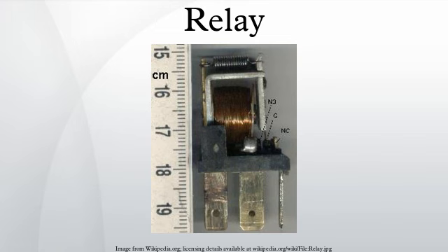Derating factors: control relays should not be operated above rated temperature because of resulting increased degradation and fatigue. Common practice is to derate 20 degrees Celsius from the maximum rated temperature limit. Relays operating at rated load are also affected by their environment. Oil vapors may greatly decrease the contact tip life, and dust or dirt may cause the tips to burn before their normal life expectancy. Control relay life cycle varies from 50,000 to over 1 million cycles depending on the electrical loads of the contacts, duty cycle, application, and the extent to which the relay is derated.